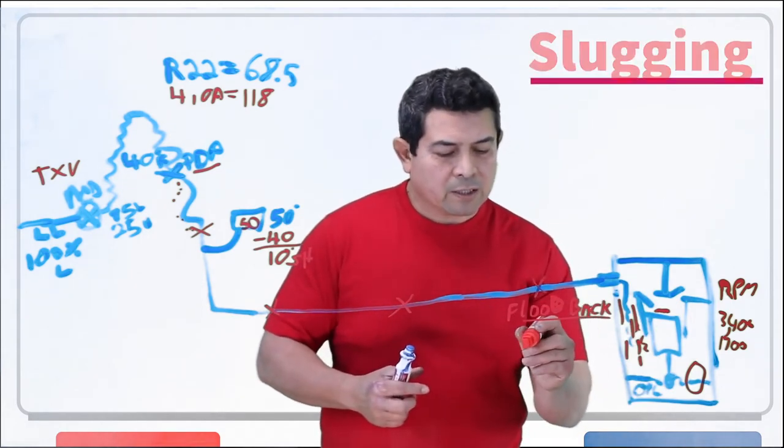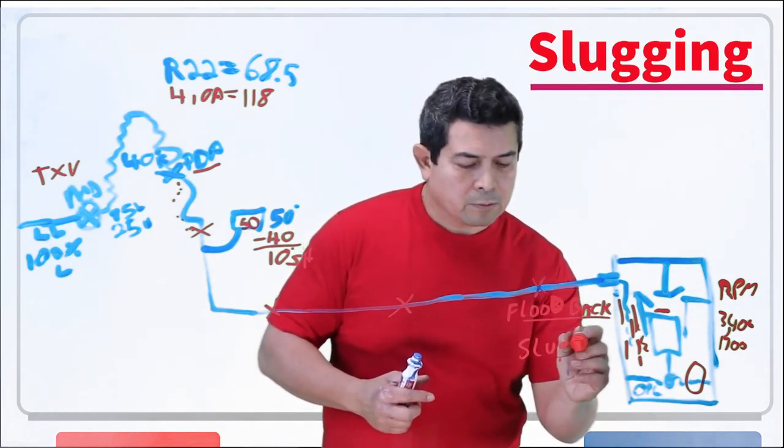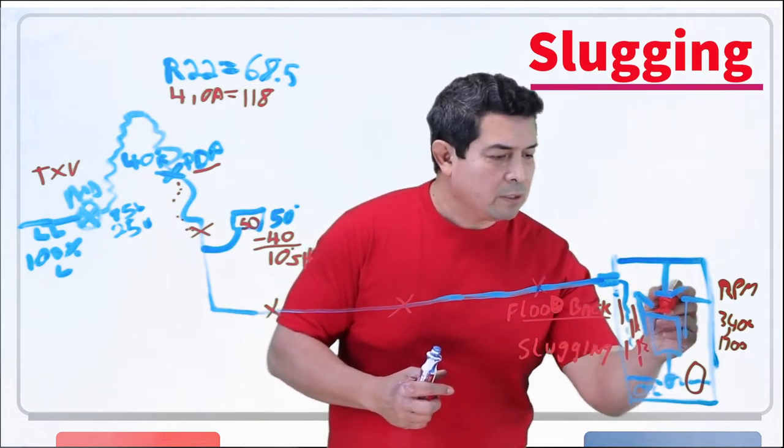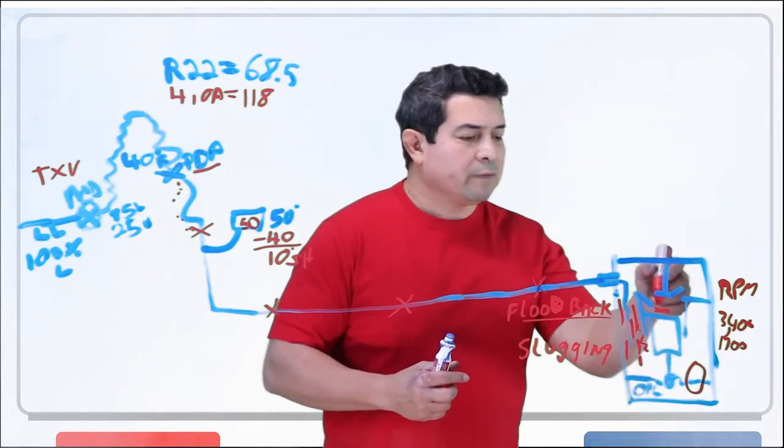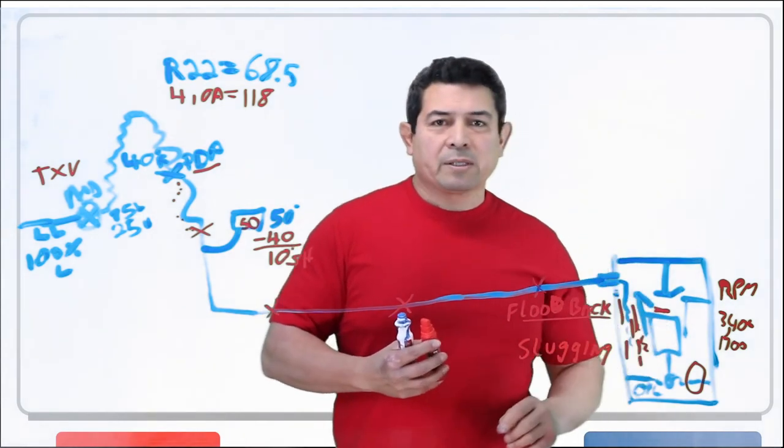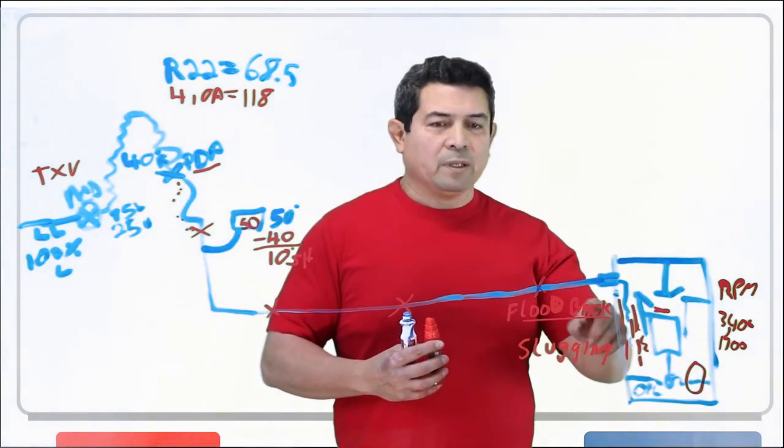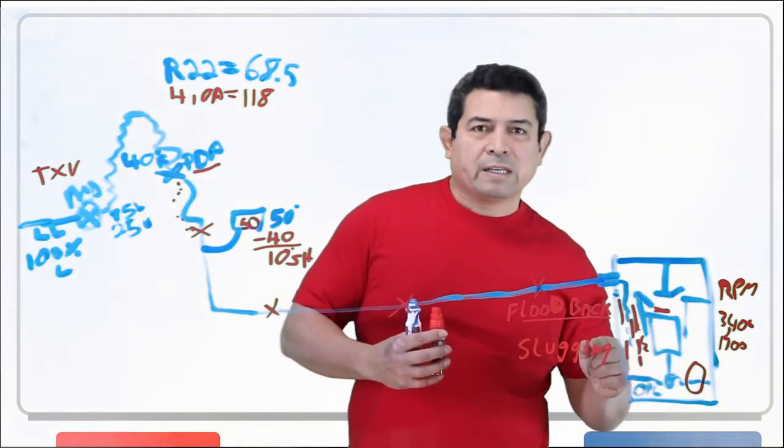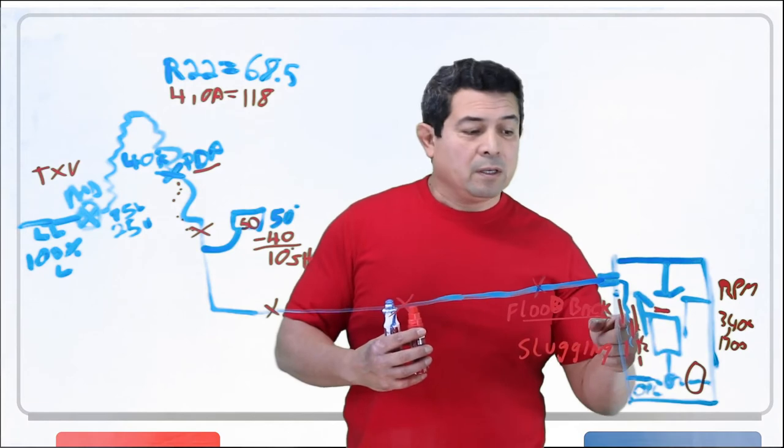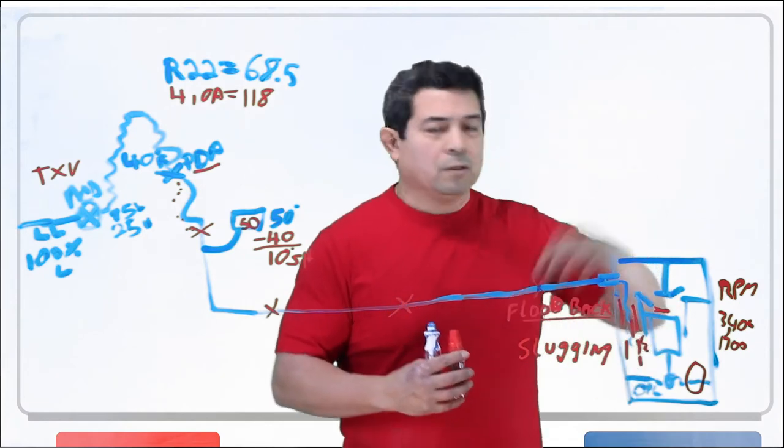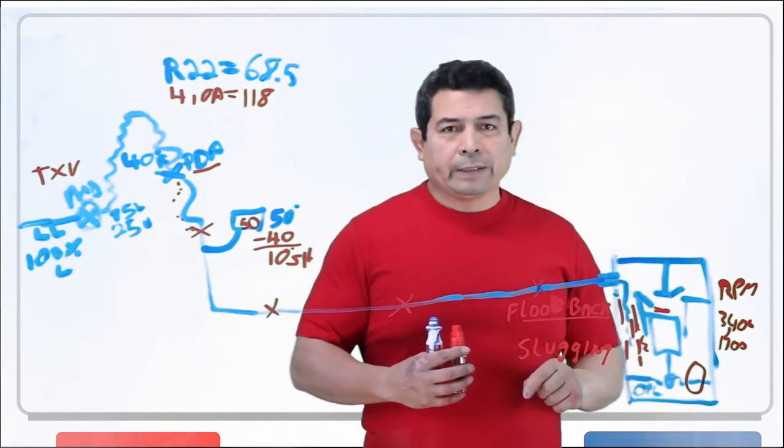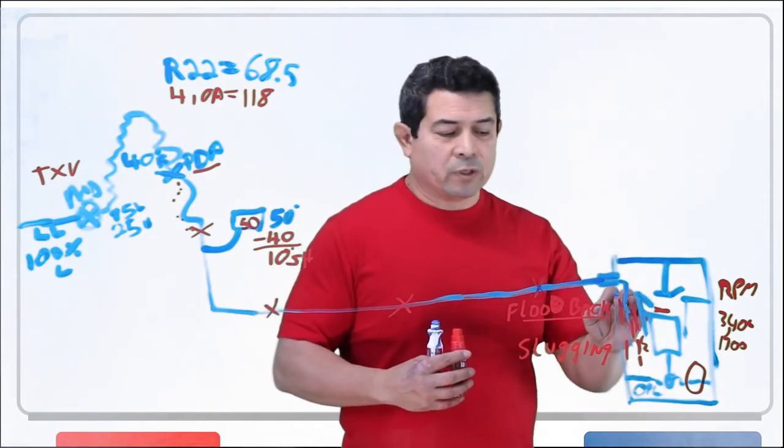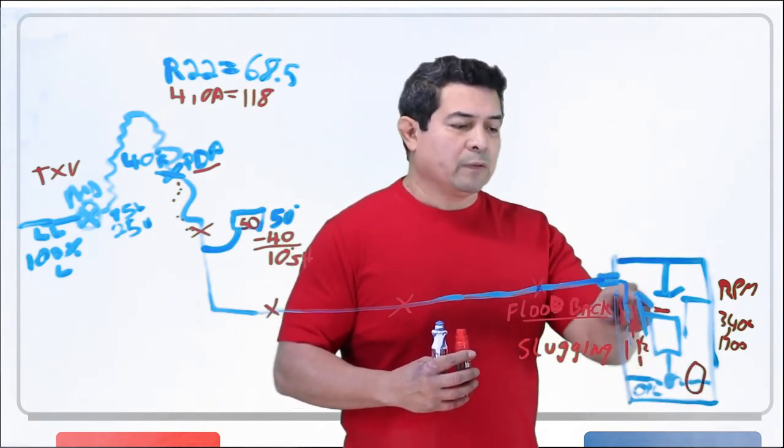Then you have what they call slugging. Slugging is when liquid gets up here. You get a slug of liquid up on top of the piston. First you get flood back, then you get slugging. That piston comes up. It cannot compress that slug of liquid in there and it's going to destroy the compressor. What kind of liquid? Well, it could either be refrigerant, liquid refrigerant, or it could be oil that's up here.